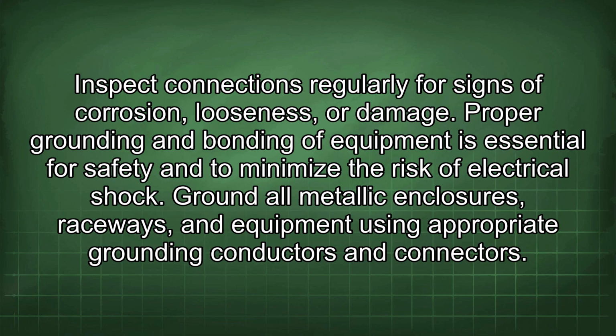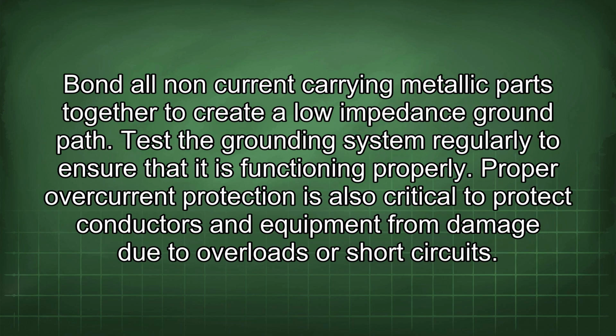Proper grounding and bonding of equipment is essential for safety and to minimize the risk of electrical shock. Ground all metallic enclosures, raceways, and equipment using appropriate grounding conductors and connectors. Bond all non-current carrying metallic parts together to create a low impedance ground path. Test the grounding system regularly to ensure that it is functioning properly.